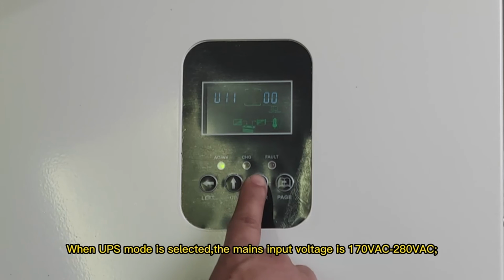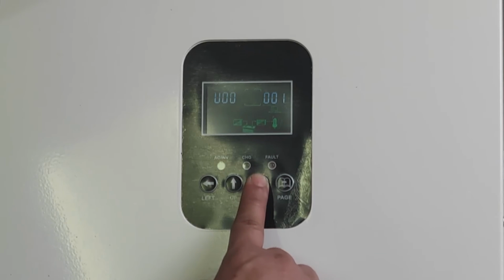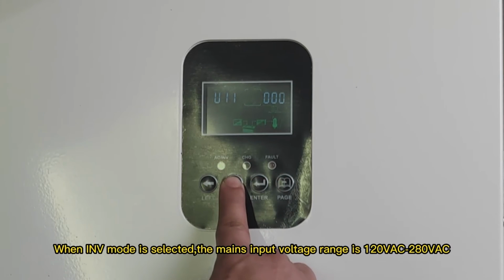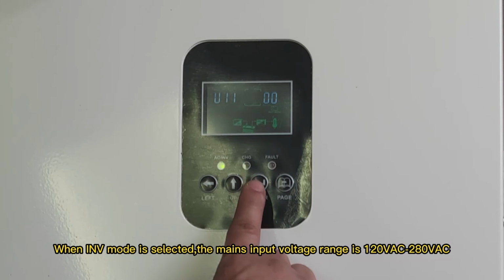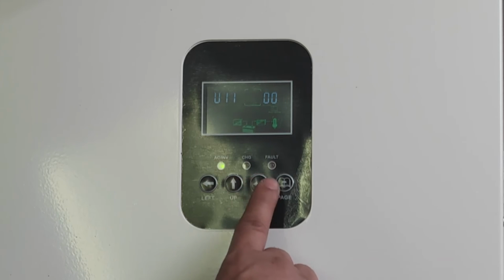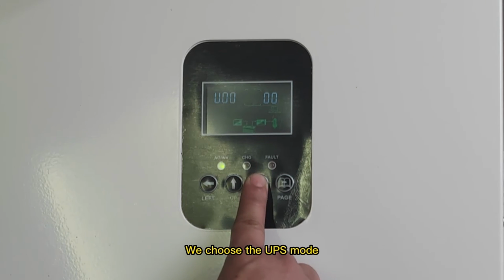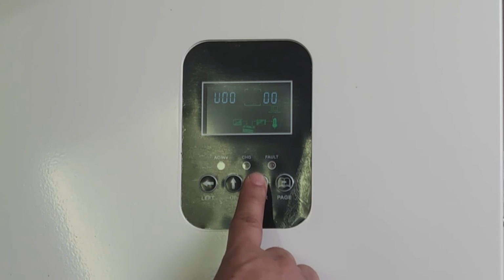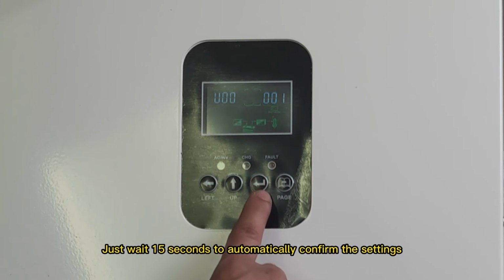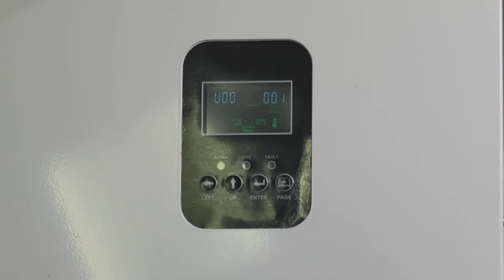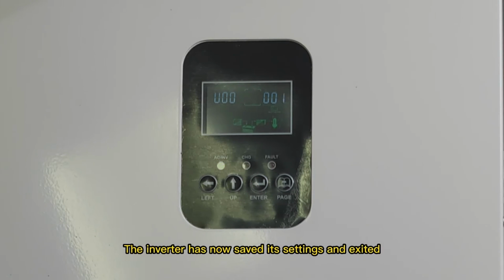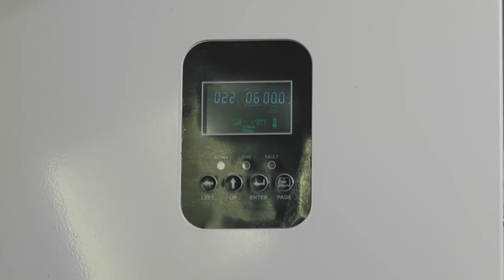When UPS mode is selected, the mains input voltage is 170 VAC to 280 VAC. When INV mode is selected, the mains input voltage range is 120 VAC to 280 VAC. We choose the UPS mode. Just wait 15 seconds to automatically confirm the settings. The inverter has now saved its settings and exited.